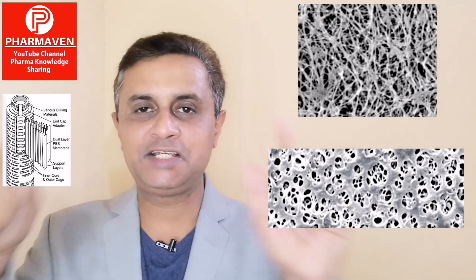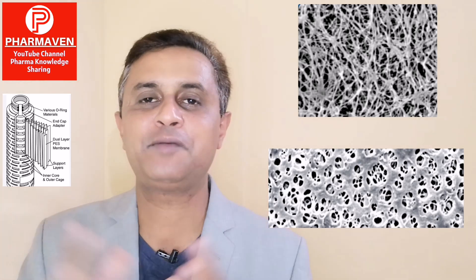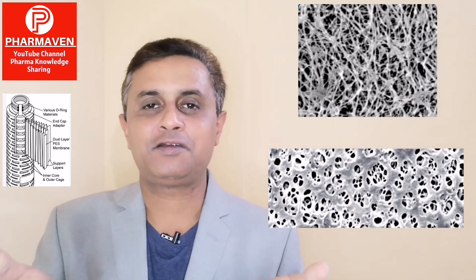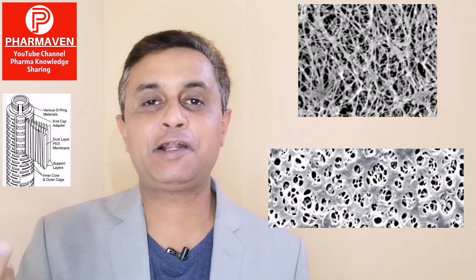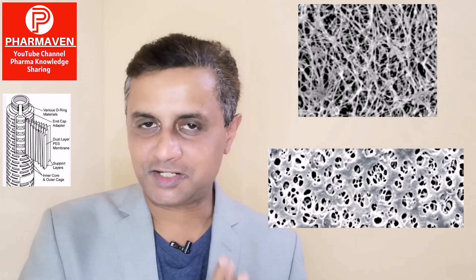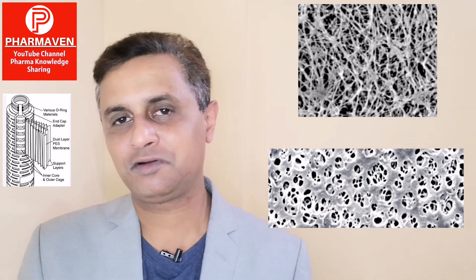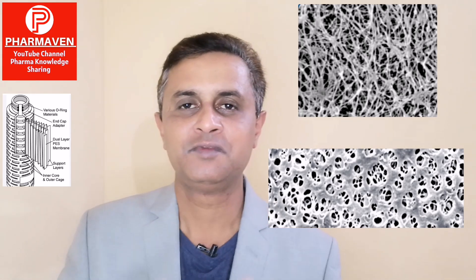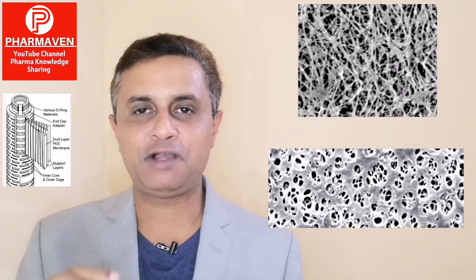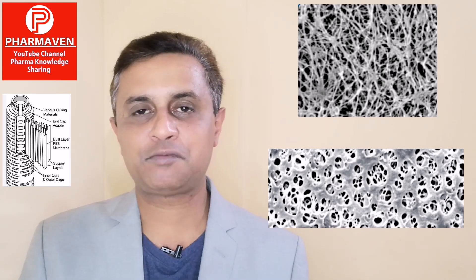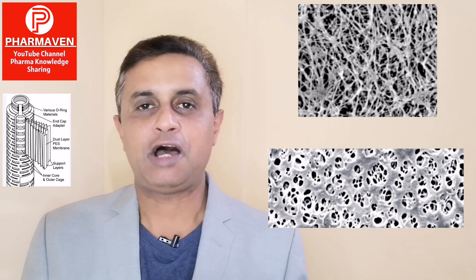The 0.2 micron filter is not a simple sieve structure — it is a complex microfiber structure. Just as we sieve fine powder to get a particular particle size through a physical sieve, in a filter achieving 0.2 micron size it is not a simple sieve. It is a complex structure of microfibers which ultimately have a pore size of 0.2 micron or smaller, giving it the capability to retain microorganisms of 0.2 micron and larger.